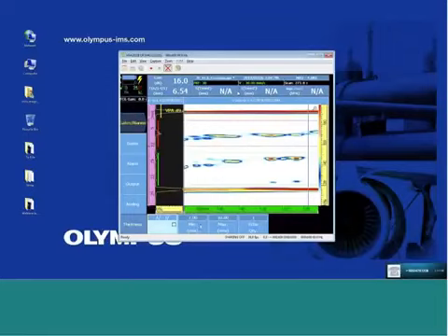And as part of our analysis after the inspection, we're going to look at the low spots, look at anomalies and missed data points, and determine where the real value is so that we can adjust the software for our statistical readings that don't interfere with the inspection from missed data points or anomalies and an invalid reading. So more to come on this shortly.